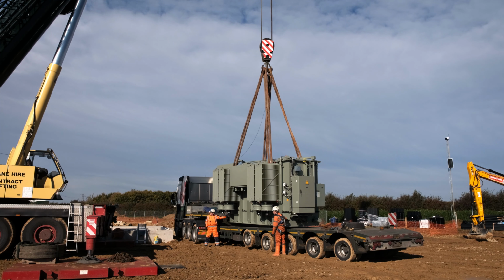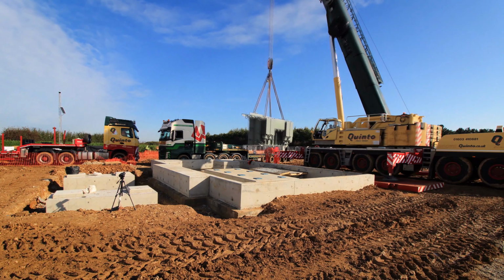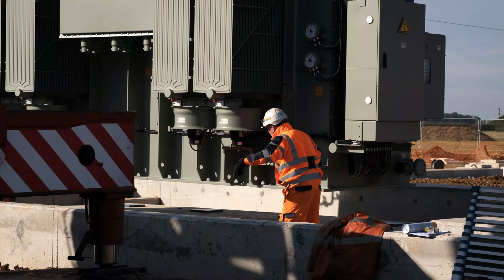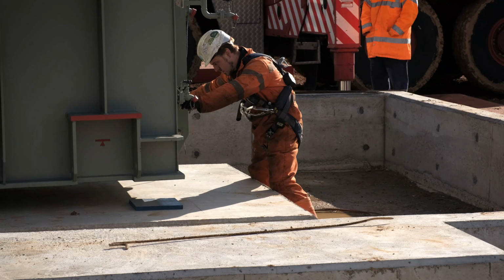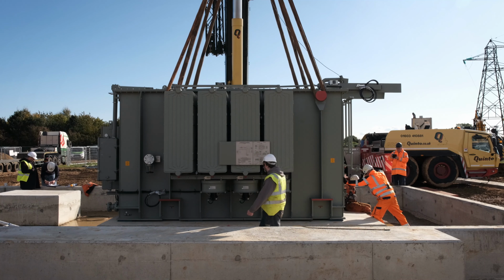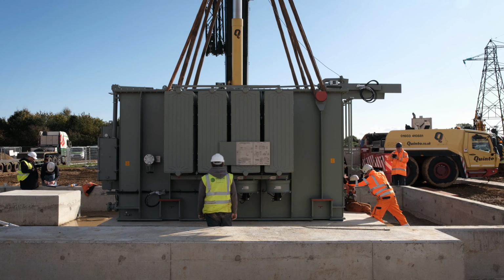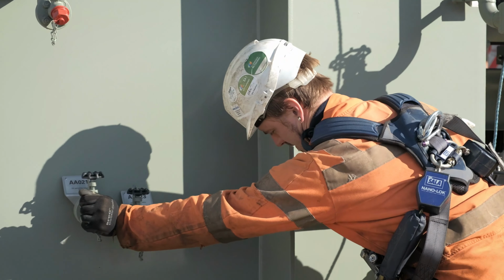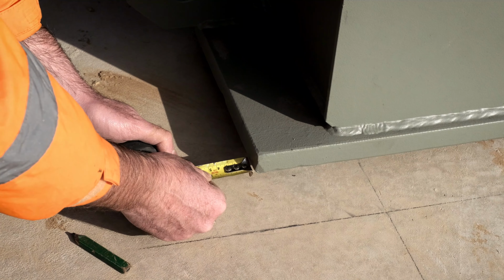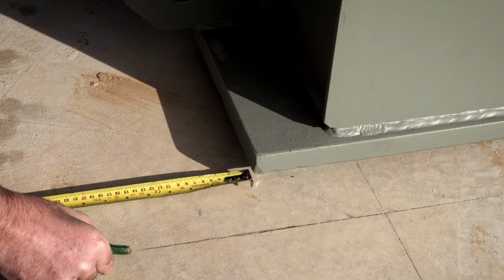Once everything's on site in front of us, we've offloaded the transformer using a 300-ton crane onto the concrete plinth specifically for the transformer. Following this, we will add the ancillary parts onto the transformer and then top it up with oil.